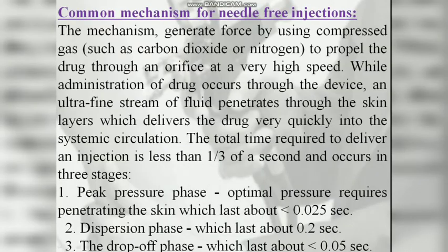Common mechanism for needle-free injections. The mechanism generates force by using a compressed gas to propel the drug through an orifice at a very high speed. While administration of the drug occurs through the device, an ultrafine stream of fluid penetrates through the skin layers which delivers the drug very quickly into the systemic circulation. The total time required to deliver an injection is less than 1/3 of a second and occurs in 3 stages. One is the peak pressure phase, second is the dispersion phase, third is the drop-off phase.